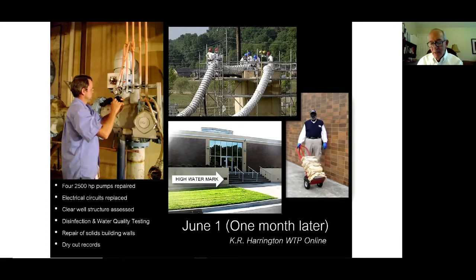Out of that comes a list of mitigation related items. We talk about relocating our generators and switchgear, adding additional generator capacity so we can run the plant at full capacity, a full 90 MGD, on generator power. We also established the need to raise the clear well vents, something we haven't done quite yet, and to seal a lot of the wall penetrations.